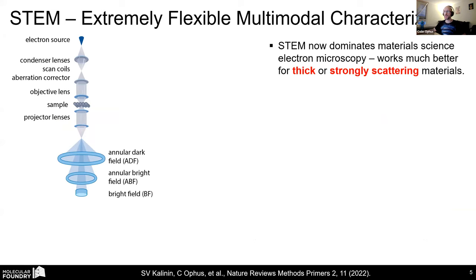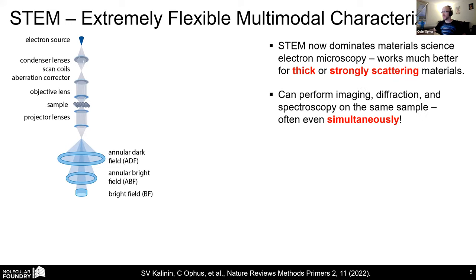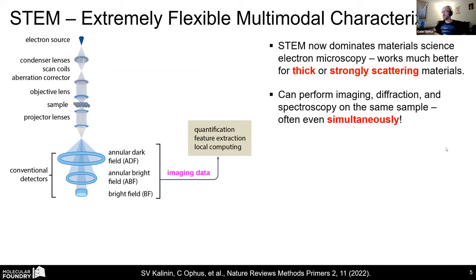We have electron sources, some condenser lenses to set up the illumination, possibly an aberration corrector, and then a very strong objective lens to get our probe down to the size we want, even subatomic scale. We enlarge the resulting diffraction pattern with a projector lens and then make measurements. Labeled here are a couple conventional detectors. These are often used simultaneously, or even with spectroscopy, to do imaging analysis. I'll show a couple quick examples of that, although not a lot in this talk.